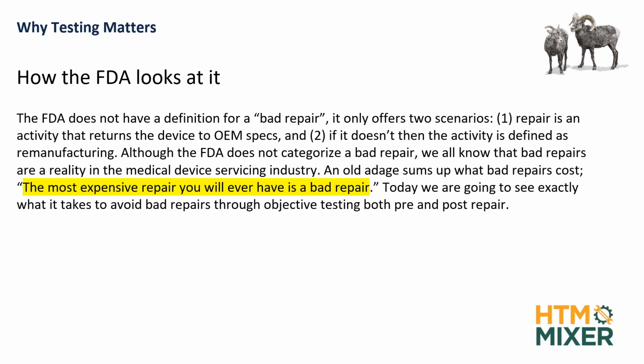So again, there's no such thing as a bad repair. They automatically say you have remanufactured the device. And if you remanufacture the device, it requires a new 510(k), which is FDA clearance, to put that product back into the sea of commerce. So FDA does not categorize a bad repair, but everyone in here has seen a bad repair, right? They call it remanufacturing so they can hold the person's feet to the fire with current regulations about manufacturing. We've seen it time and time again, and I'll show you a couple of examples.